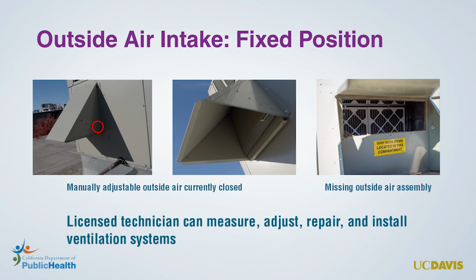Conversely, the system depicted on the right lacks its outdoor air intake assembly entirely, leading to the unintended consequence of drawing in nearly 100% outside air continuously. Fixing this requires installing and configuring the outdoor air assembly to achieve the desired outdoor airflow.